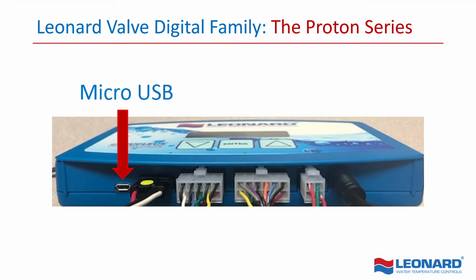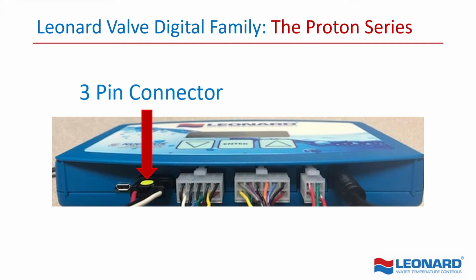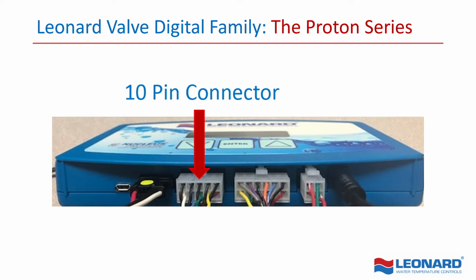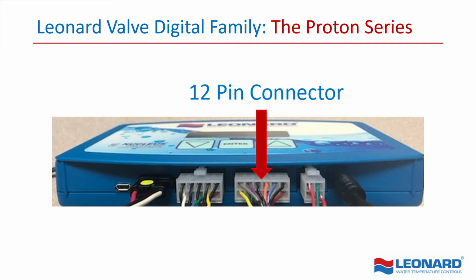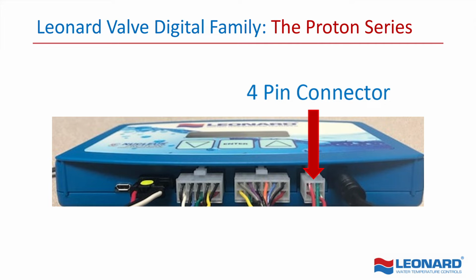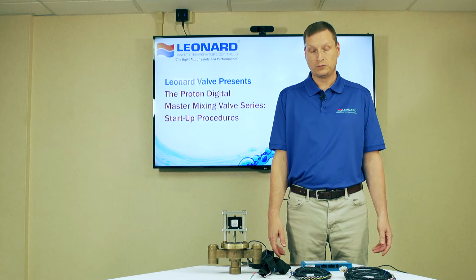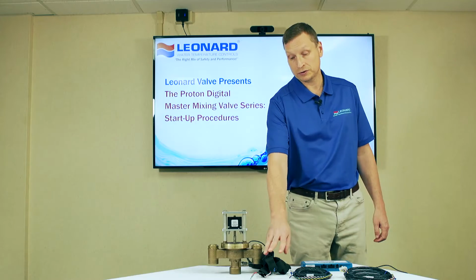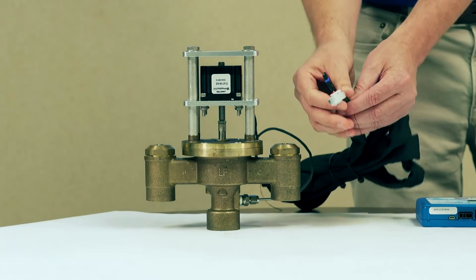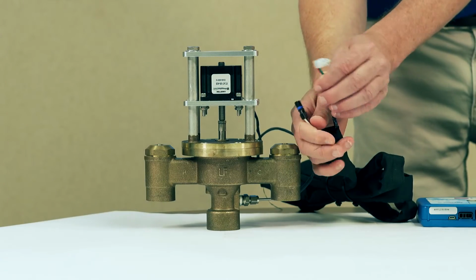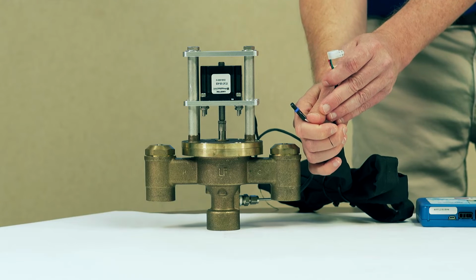Connections go from left to right: micro USB, 3-pin RTD, 10-pin relay, 12-pin BMS/temperature sensors, 4-pin motor connection, and power cable. Before powering up the unit, you need to make sure you plug in your 4-wire motor connection and your 3-wire RTD. From that point, you may power up the unit.